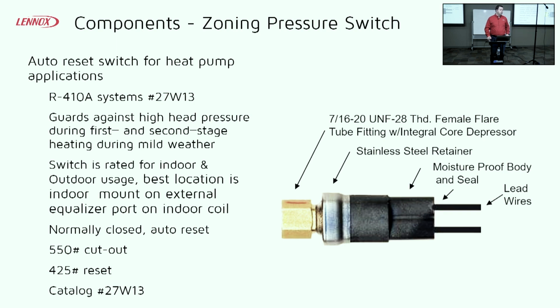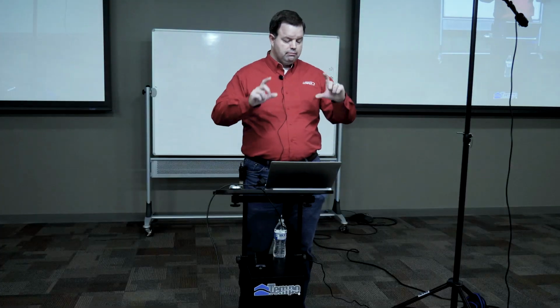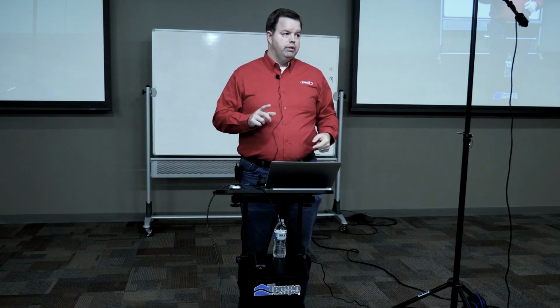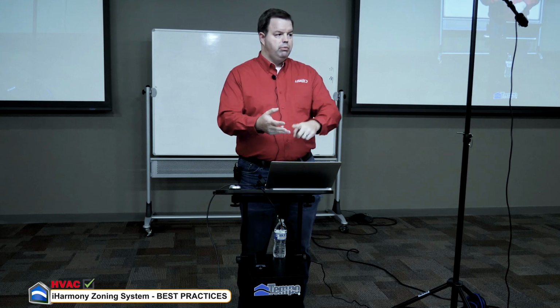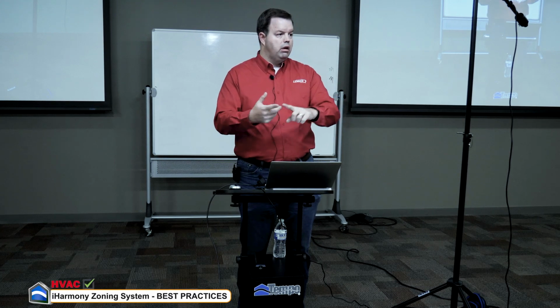Yes, sir. Where the control, like the S30 thermostat, will it tell you the pressure? Will you be able to see the pressure, or will you have to tie in your gauges? It won't show you, it's not a pressure transducer, but you can look at a diagnostic screen that will show you the status of this switch. Basically, if you have a fully communicating system like this, there's a diagnostic screen where you can look at all the inputs for the zone system: your discharge air temp, this switch, a freezestat if it's installed, your zone temperatures, all that information.